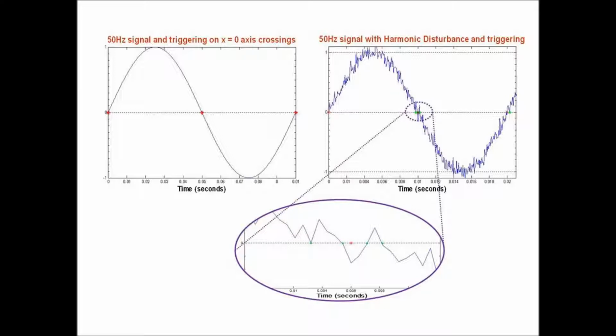There's a 50 Hz signal. Some power converters use the zero crossing, so where it goes from positive to negative, as a firing point for whatever they're doing in your converter. So every time it goes from high to low, you have a pulse. And what ends up happening is if you've got a harmonic like that happening at the same time as your pulse, you might not necessarily get the same crossing points. So in this case, you actually miss the designated point and have 2 more or 4 more crossings nearby, which is equivalent to about 750 Hz or thereabouts. So instead of having a 50 Hz signal, you've got what your converter thinks is a 750 Hz signal, which isn't particularly good for any electronics.